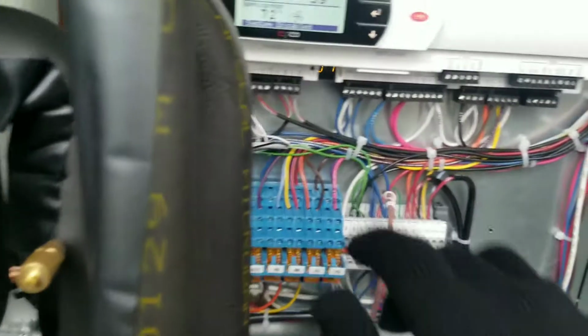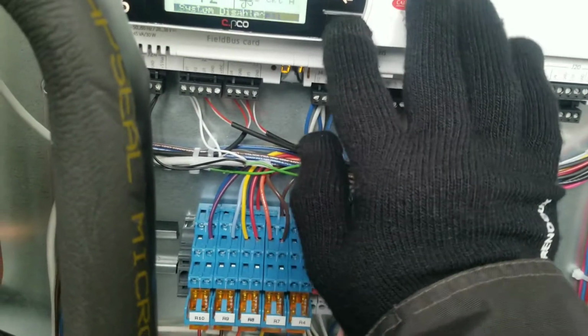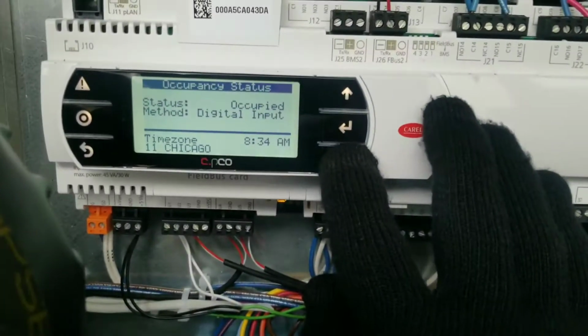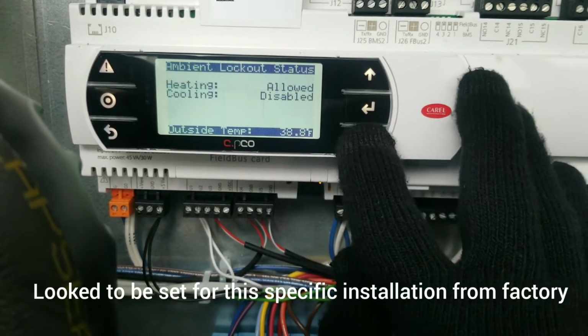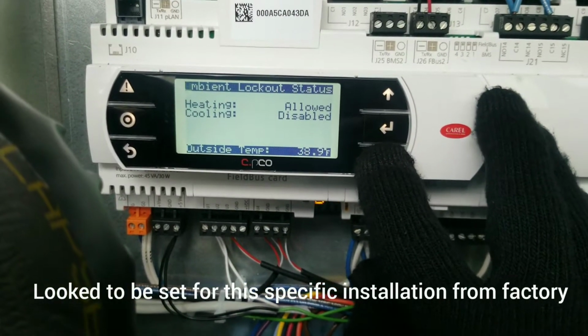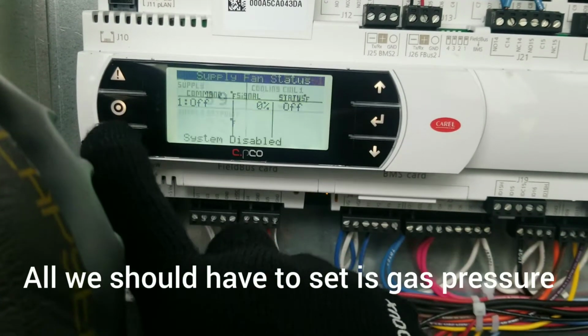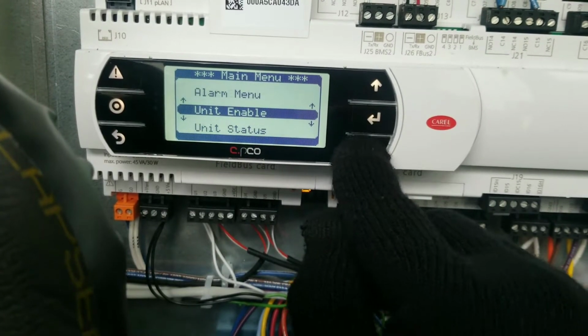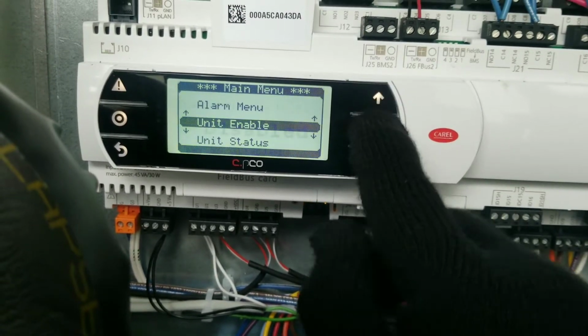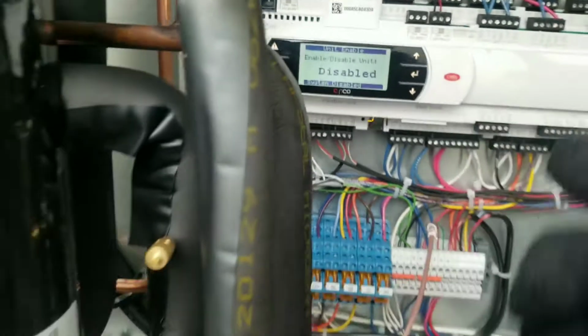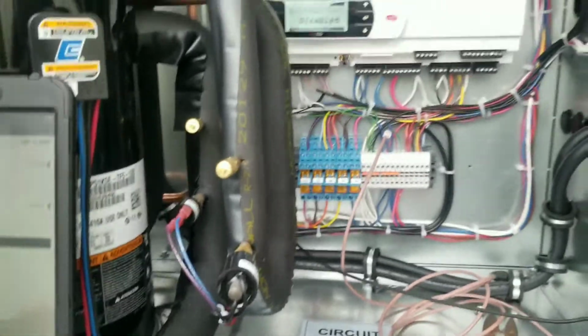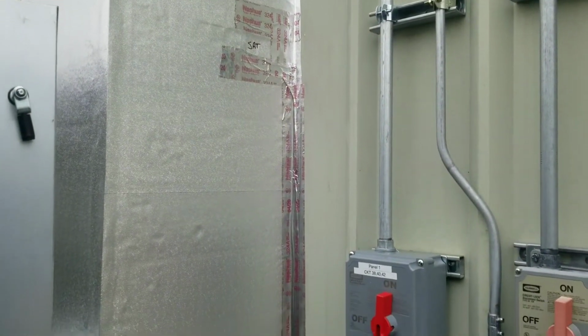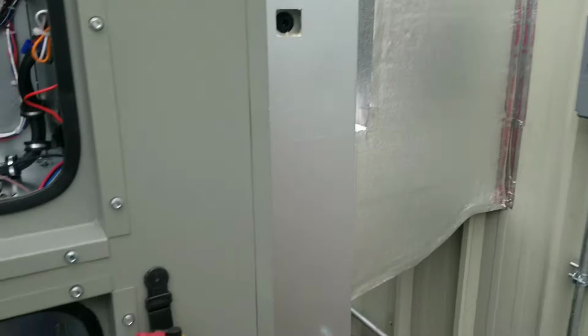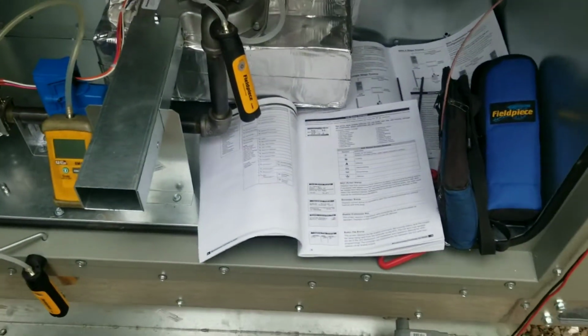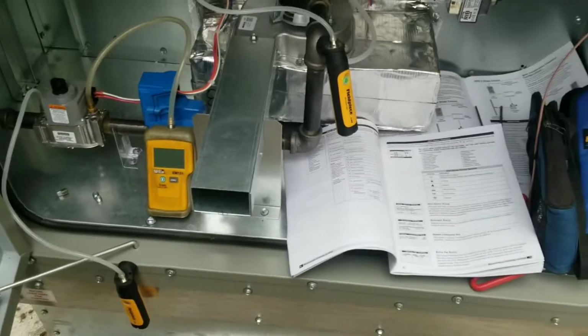I got my manometers ready. My system's disabled right now, and looks like this control is going to do just about everything. It's cooling disabled there, and the heating is allowed. So I'm going to have to basically go into my unit enable and enable the unit, and that should bring the heat on, and supply temperature set at 72. So I had some installers here, so I had them go ahead and move the supply sensor and get it mounted.